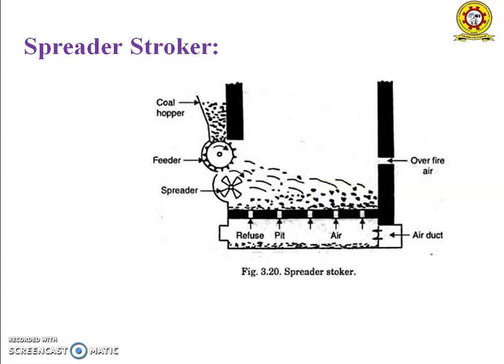This type of stoker can be used for boiler capacities ranging from 70,000 kg to 140,000 kg of steam per hour. The heat release rate of 10 × 10^6 kilocalorie per meter square hour is used. The speed of the stoker is 15 to 50 cm per minute. The coal bed thickness is shown at all times by an index plate, which can be regulated either by adjusting the opening of the fuel gate or by speed control of the stoker driving motor.